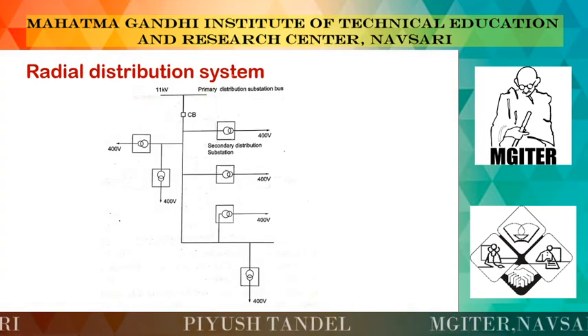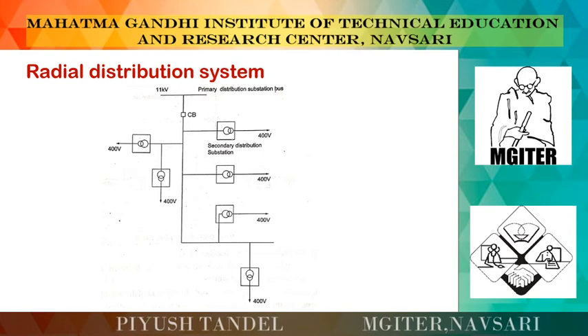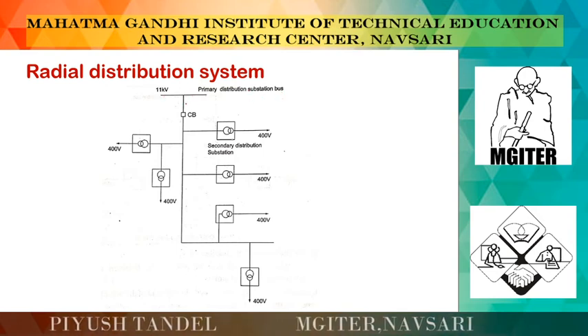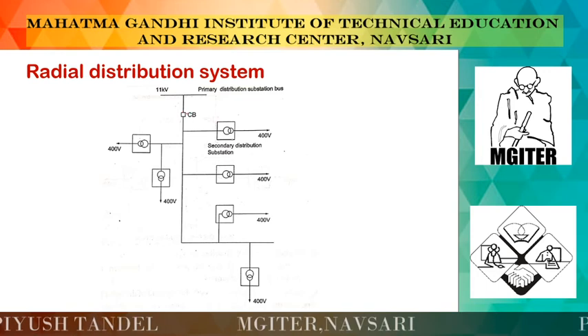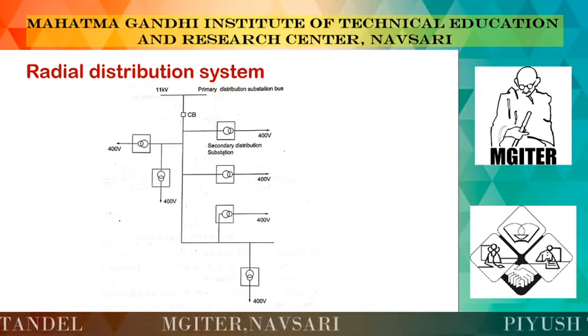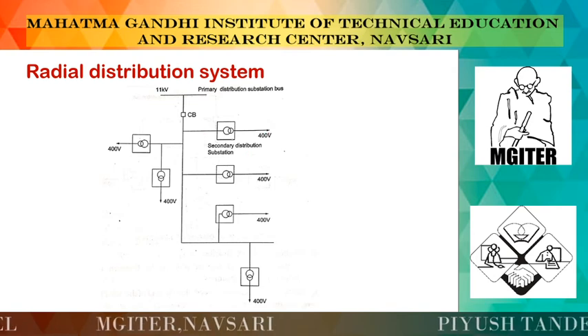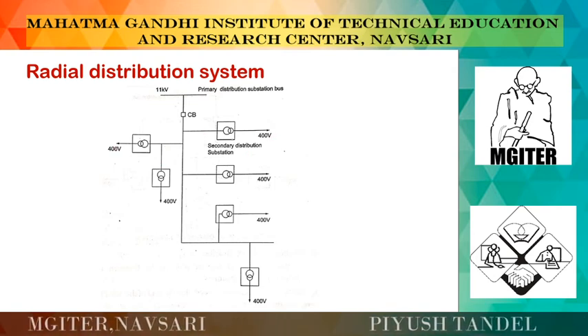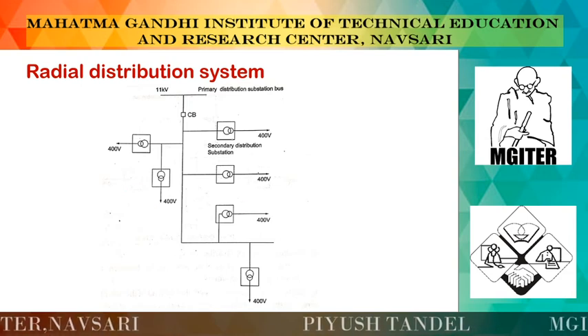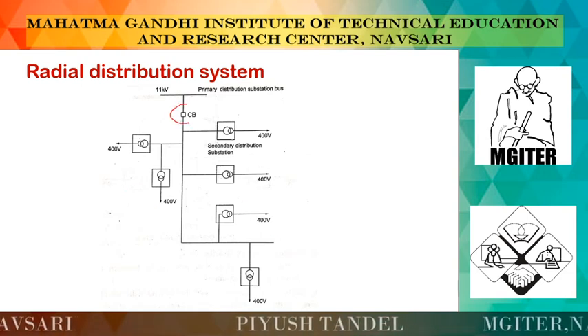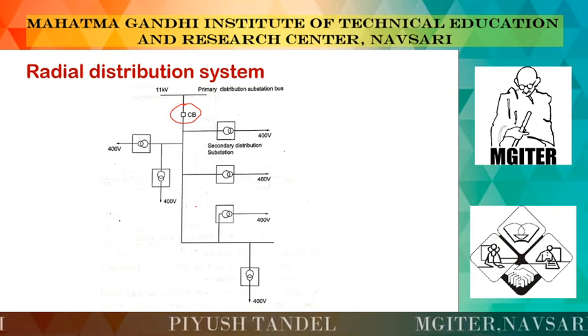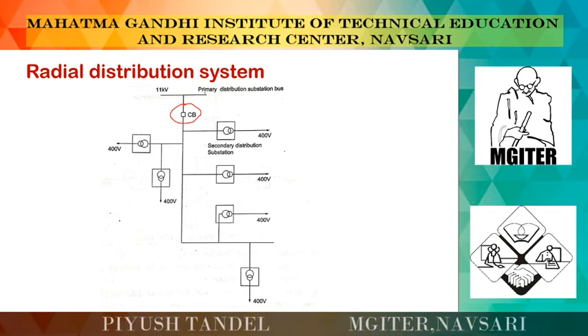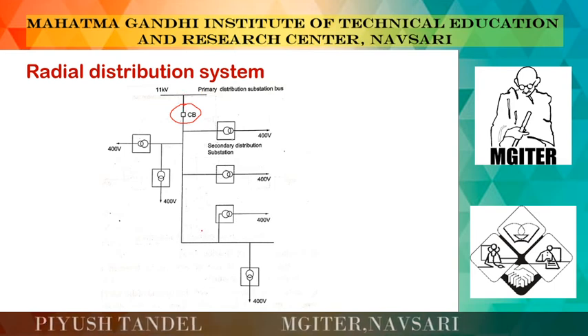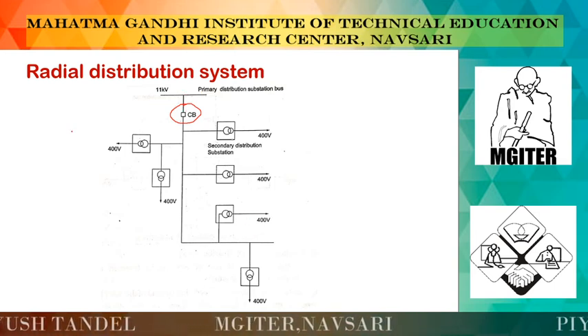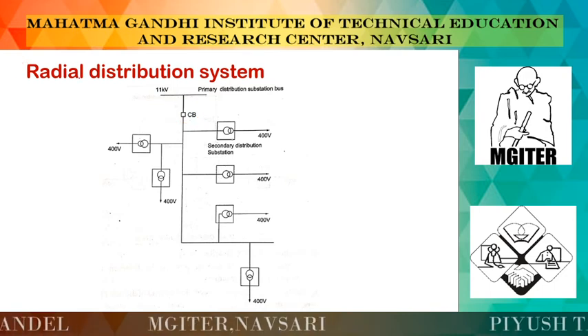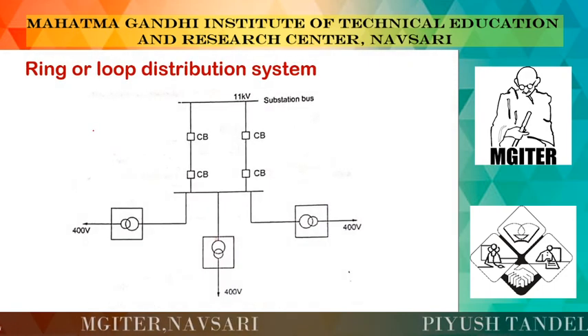In the radial distribution system, we have the primary distribution substation, which is connected to different types of loads. We have a circuit breaker first of all, then we take the tapping for the secondary distribution system, which converts 11 kV to 400 volts. Again over here we convert 11 kV to 400 V, and so on. We only have this one circuit breaker between the load side and the 11 kV distributor side. That is the radial system. Inside the radial system only one single path is available for the power supply, which is why it is called a radial distribution system.